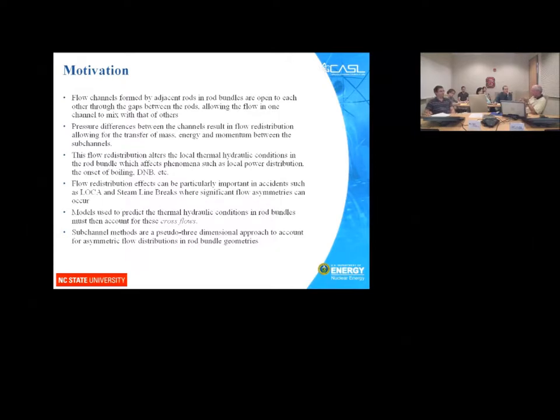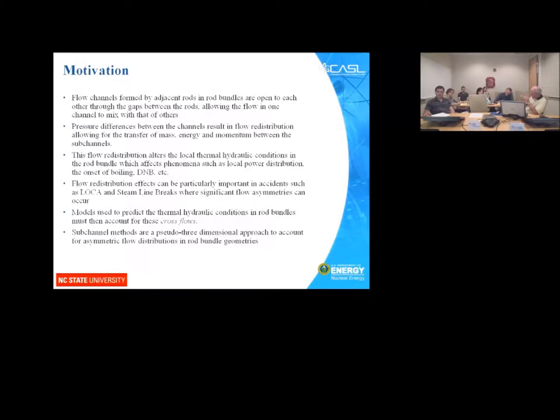The fluid distribution or energy distribution changes at what point on the local rod surface you will begin to boil — which is extremely important for some CASL challenge problems. For example, for crud, they're interested in where boiling begins. If you miss where boiling starts by several feet or meters, you've missed the whole problem. One challenge problem involves departure from nucleate boiling or critical heat flux, and the local fluid parameters directly impact where and if that occurs.